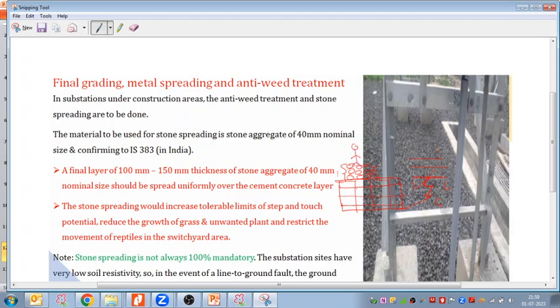So this stone is increasing the contact surface resistance between the person's feet and the ground. If this contact resistance is increased, the probability of the fault current reaching the person is very low, and the person would be saved under fault conditions, right? This is what the stone is doing. Is it making some sense? Yes, sir, for safety, yes.